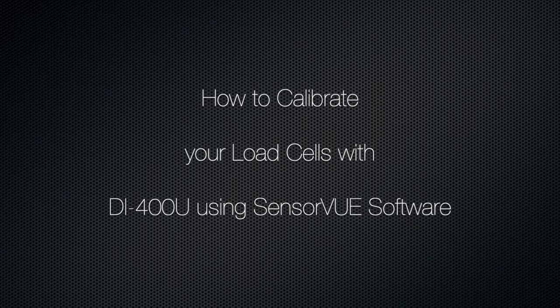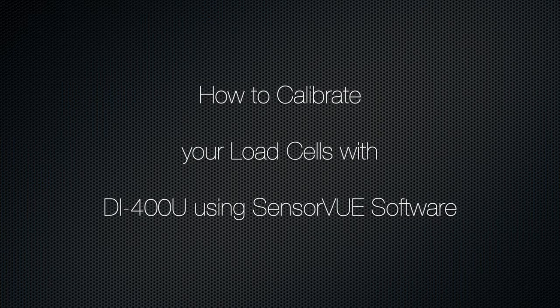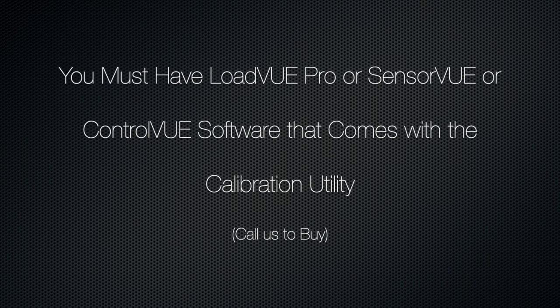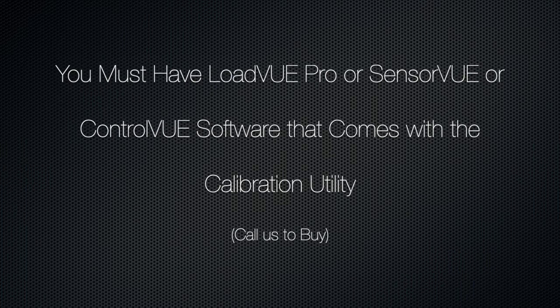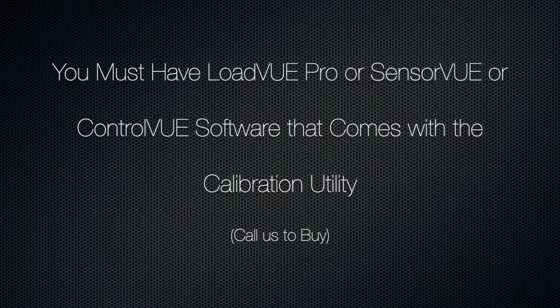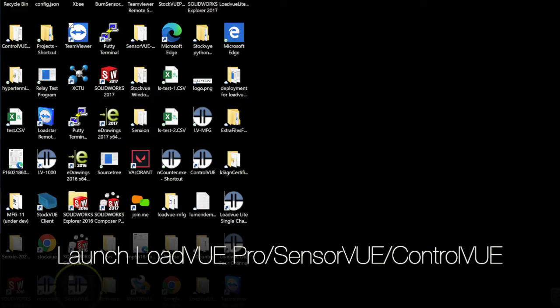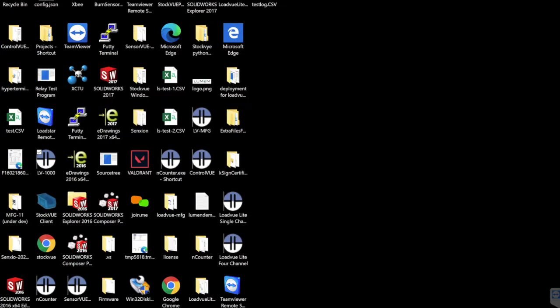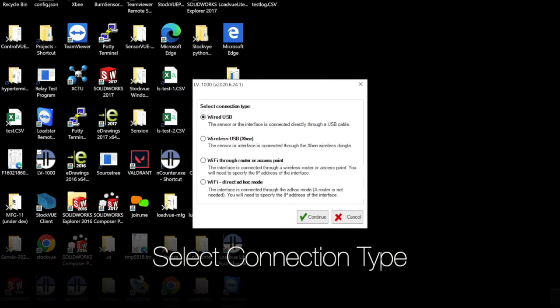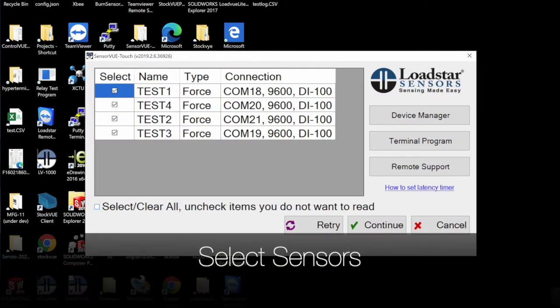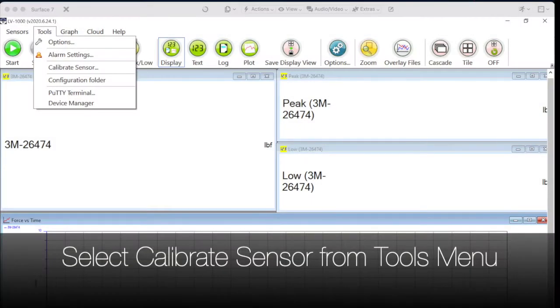Before you can use our digital interface with your load cells, you must calibrate them. You can use the utility built into our software to calibrate your load cells to DI-400U. You must calibrate one load cell at a time. Launch the program. You could use either LoadVUE Pro or SensorVUE or ControlVUE. Select the connection type. Select the sensor you want to calibrate. You will need to calibrate one sensor at a time. From the Tools menu, select Calibrate Sensor.